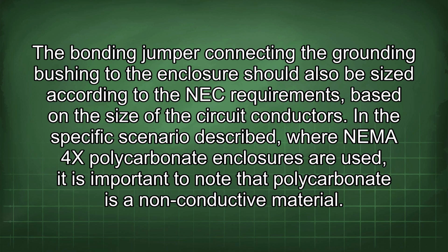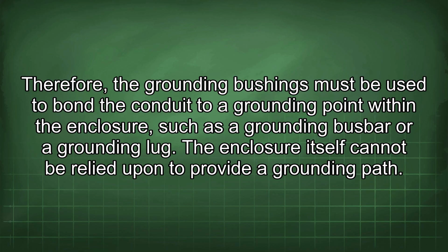In this specific scenario, where NEMA 4X polycarbonate enclosures are used, it is important to note that polycarbonate is a non-conductive material. Therefore, the grounding bushings must be used to bond the conduit to a grounding point within the enclosure, such as a grounding busbar or a grounding lug. The enclosure itself cannot be relied upon to provide a grounding path.